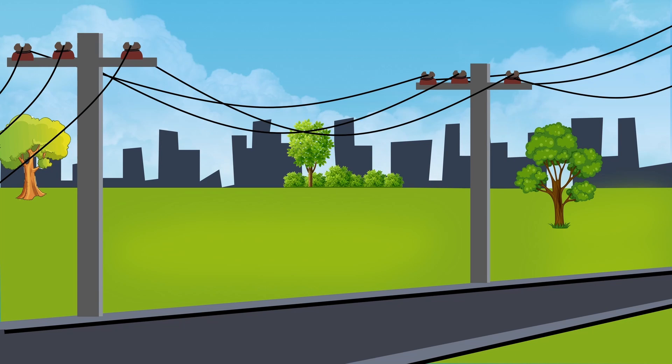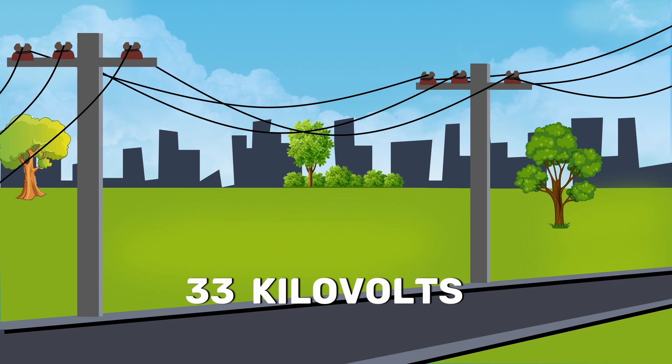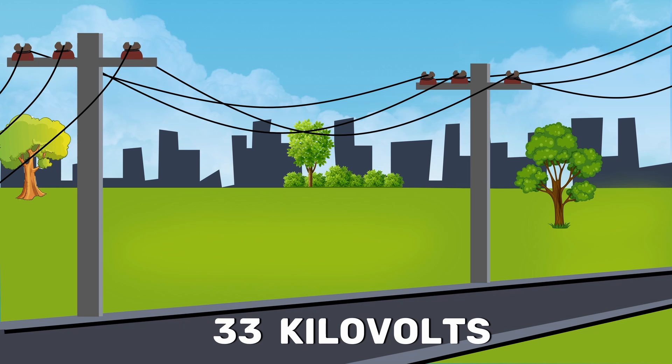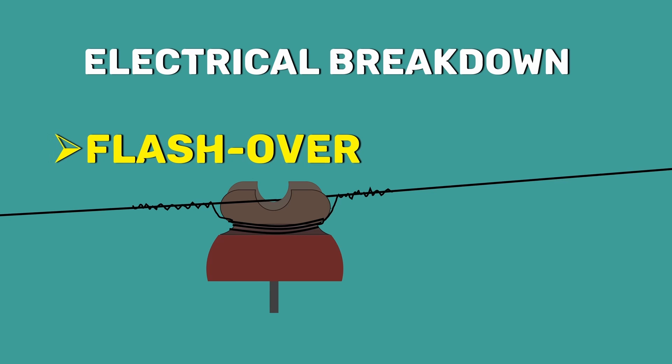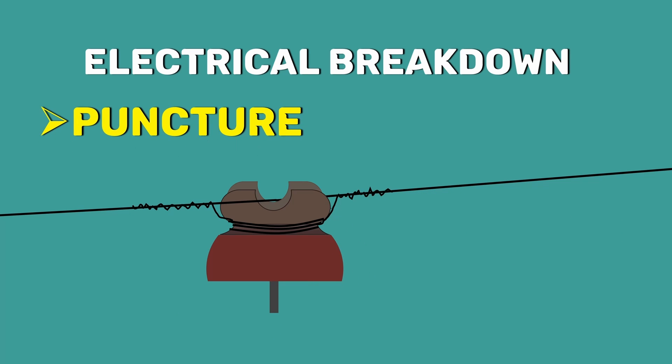So, the pin type insulators are used at voltages up to 33 kV. Even after designing an insulator considering all these factors, there are times where we cannot avoid the electrical breakdown. The electrical breakdown occurs as either a flashover or a puncture. In a flashover, an arc occurs between the power line and the insulator pin through the air, while during puncture, the arc travels through the insulator body.